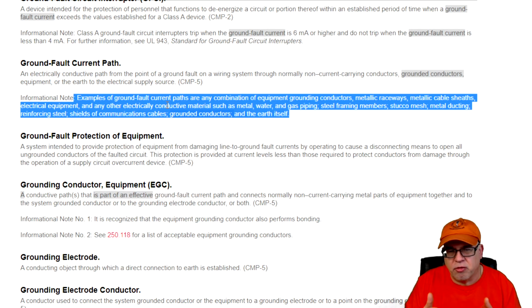Don't get confused by the informational note, because some of those things they list aren't necessarily low impedance. They could still be a ground fault current path because they're conductive, but they're not low impedance. So again, this is a great example where the informational note is just trying to give you some understanding. Don't lose sight of when we need a low impedance ground fault current path. That is where we need to make sure we're using equipment grounds, equipment bonding jumpers, and metal raceways that are listed in 250.118. Don't let this imply to you, and of course informational notes aren't enforceable anyway, that the earth is an acceptable path. It's not, in our case, for the National Electrical Code. It isn't. Just want to make that clear.